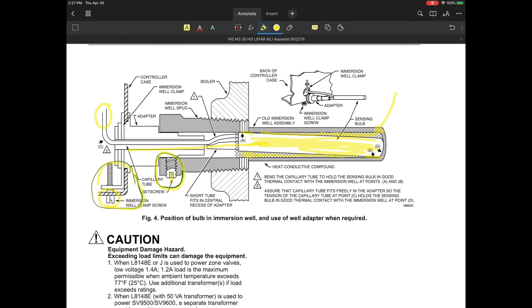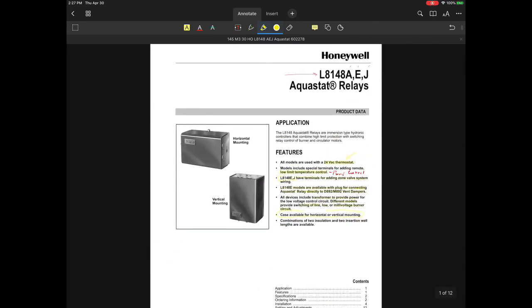I wanted you guys to see this because my concern is that if you go onto one of these and you have a defective Aquastat and you have to replace it, I've seen guys in the field who have taken these Aquastats and loosened this screw, this little immersion well clamping screw, and started to twist out the Aquastat. And all they were really doing was breaking this little capillary tube, and then they still ended up having to take that out. Now, if the well or the Aquastat is defective, I guess then it's nothing to worry about. You're replacing it anyway. But just so you know, that's kind of the process of how they do that.